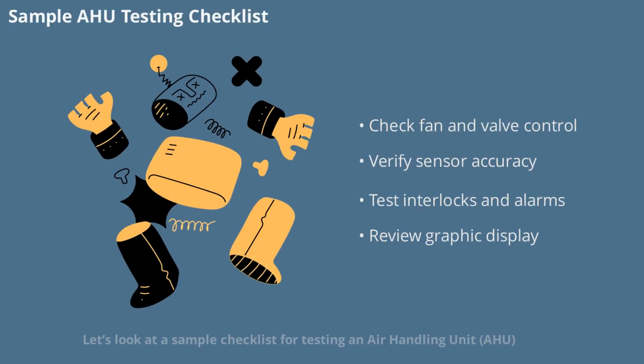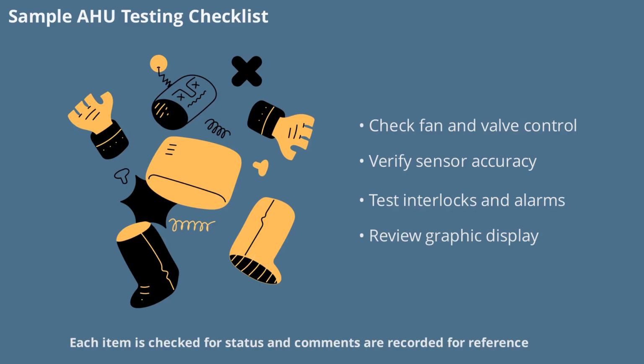Let's look at a sample checklist for testing an air handling unit, AHU. Key items include verifying supply fan on-off control, checking the accuracy of the supply temperature sensor, and ensuring the cooling valve operates correctly. We also test the chilled water flow interlock, PID loop tracking, high temperature alarms, and confirm that the graphic display shows live data. Each item is checked for status and comments are recorded for reference.